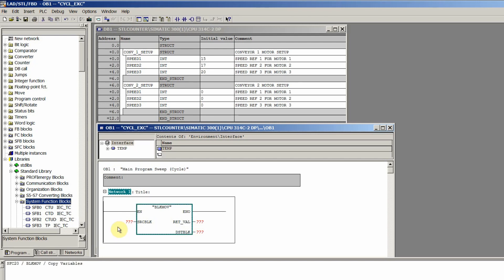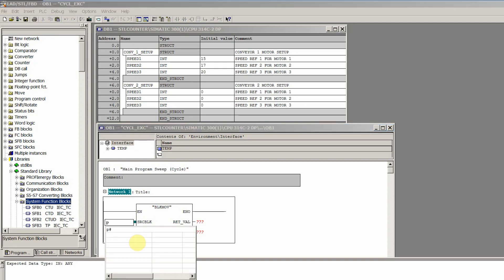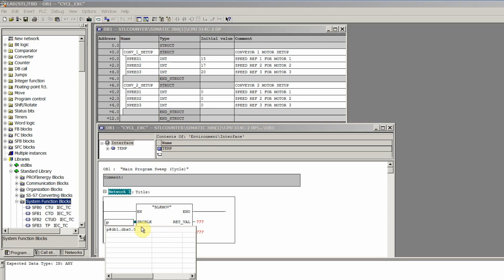To use the pointer we write the command P# — P is for pointer and # is its syntax. We write DB1.DBX 0.0 — the 0.0 represents the first bit of this structure, indicating from which bit the copy or move starts. Then we press space and write BYTE 6, since the first structure has six bytes. Pressing Enter, we can see that it has selected the conveyor one motor setup structure.